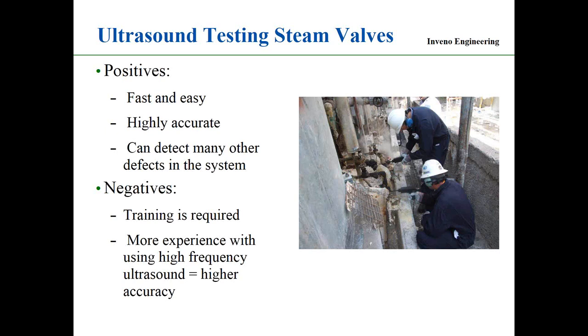The positives: fast and easy, highly accurate, and can detect other defects in the system — also used for testing steam traps. The negatives: training is required, but any tool used in a steam system requires training. High-frequency ultrasound is like riding a bicycle — the more you ride, the more proficient you get. The more experience you gain, the more accuracy you achieve.